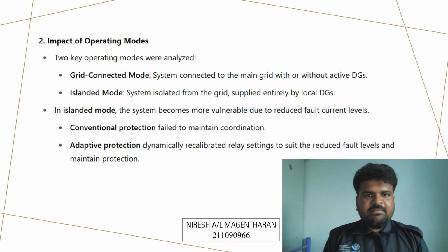So the second point is impact of operating modes. Two key operating modes were analyzed, which is grid connected mode, system connected to the main grid with or without active DGs, and islanded mode, system isolated from the grid, supplied entirely by local DGs. So in islanded mode, the system becomes more vulnerable due to reduced fault current levels. The first one, conventional protection failed to maintain coordination. Adaptive protection dynamically recalibrated relay settings to suit the reduced fault levels and maintain protection.